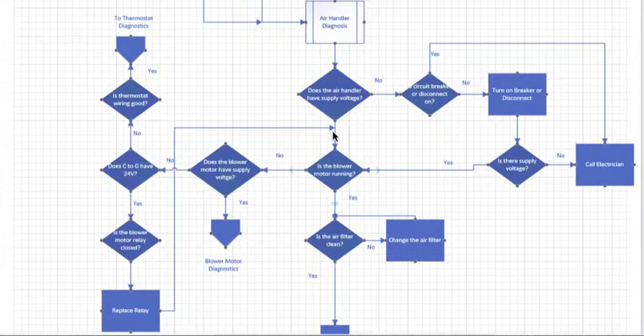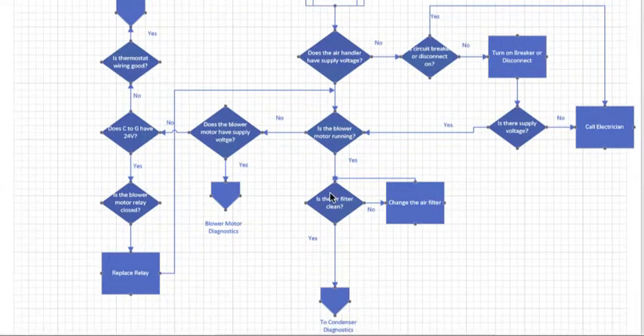So now we have a blower motor that should be running. If you did this whole process properly, your blower motor at this point is running. Might be a new motor, might not be a new motor. So now you should have a yes on the blower motor is running. Check the air filter. Is it clean? If it's not clean, change the air filter. Then come back. Is the air filter clean? Once you're completely done with your air handler diagnostics, then you can move on to your condenser, and we'll talk about that in another video.